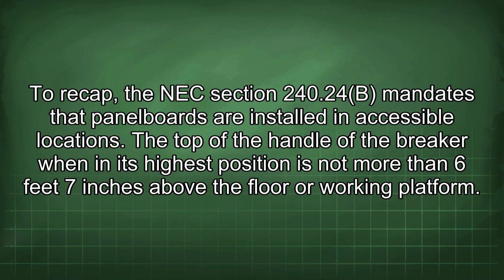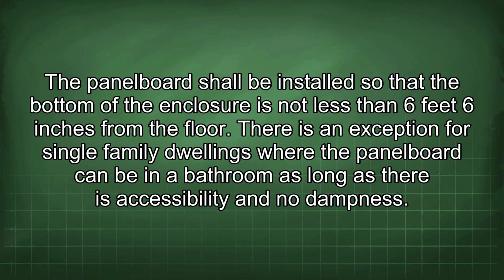To recap, the NEC Section 240.24(B) mandates that panel boards are installed in accessible locations. The top of the handle of the breaker when in its highest position is not more than 6 feet 7 inches above the floor or working platform. The panel board shall be installed so that the bottom of the enclosure is not less than 6 feet 6 inches from the floor. There is an exception for single-family dwellings where the panel board can be in a bathroom as long as there is accessibility and no dampness.